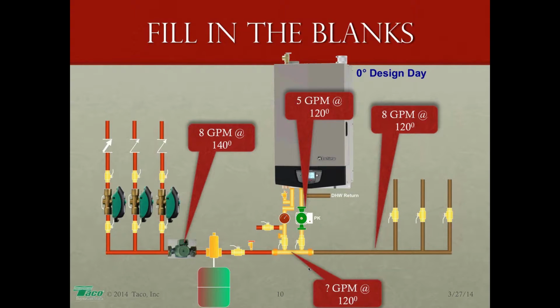The question now is, how many gallons per minute of 120-degree water do I have going between those two T's, which is the common piping? Well, that's math. If I've got 8 going into one end of the T and I'm yanking 5 out, I've got to have 3 gallons per minute coming out the other end. Simple rule: what goes into a T has to come out of a T through a combination of the two holes. So I've got 8 gallons a minute entering the T, 5 gallons a minute going to the boiler, and 3 gallons a minute of 120 proceeding through the common piping into that second T, which is now a mix point. I've got 5 gallons a minute going to the boiler, being heated up, 5 gallons a minute coming out of the supply line, and that 5 gallons a minute of something is going to mix with 3 gallons a minute of 120, hopefully to give me 8 gallons a minute worth of 140 degrees.